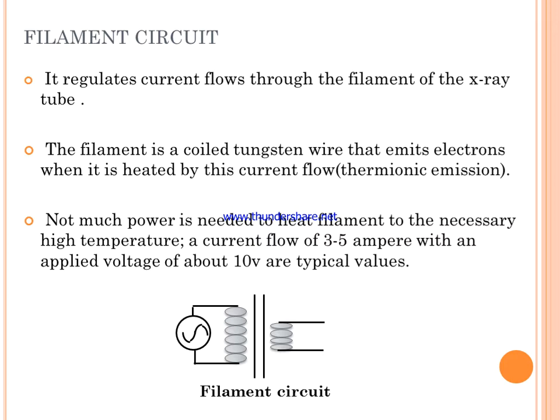The filament circuit regulates current flow through the filament of the X-ray tube. The filament is a fine wire that emits electrons when heated via thermionic emission. Not much power is needed — a current of 3 to 5 amperes with an applied voltage of about 10 volts at typical values. Here is an image showing the filament circuit.